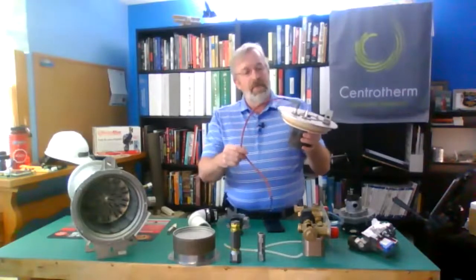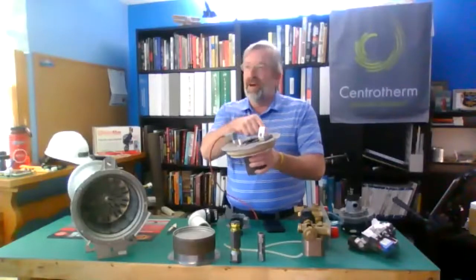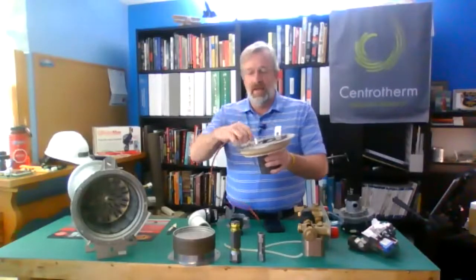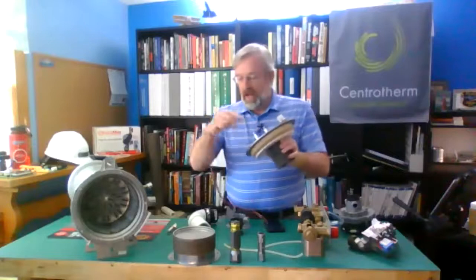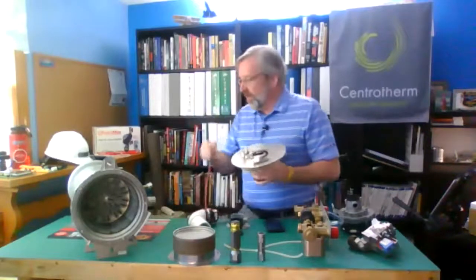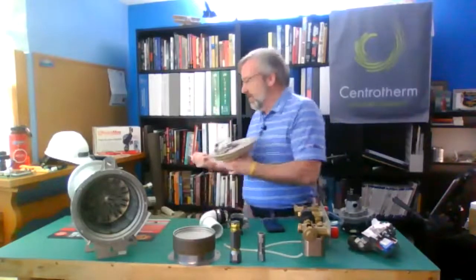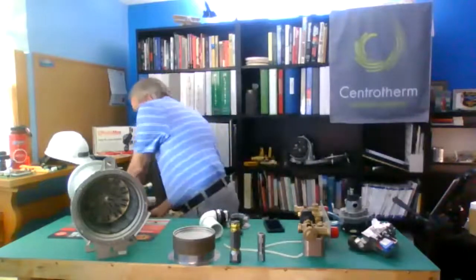So I want to look for spark here when I'm going through that ignition cycle. So if I'm not certain if it's sparking, and every once in a while it's kind of hard to tell from sight glass to here, go ahead and disconnect your igniter from the top. And that's a T20 Torx head screw. So go ahead and remove that.